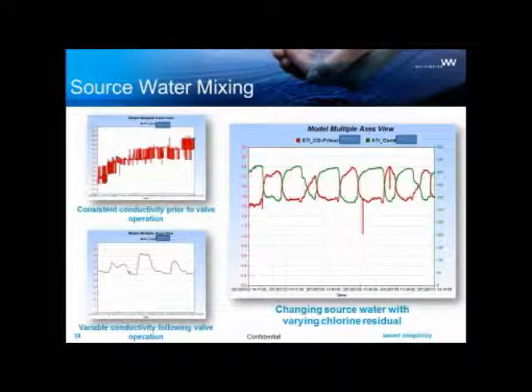Now again, going back to the mixing of the source of water, this is an important issue in several territories around the world, in the US, in Europe, in China, in Japan, in Australia, and here in Israel, where we have continuous changes of the water sources, causing a lot of false alarms. You can see here an example of the chlorine and the conductivity, with a very nice example of how the BlueBox detects a change in your water source. The BlueBox says, that's right, we've changed the water source, but we are still in a normal situation. The water is good. This is, if you will, a go, no-go situation.